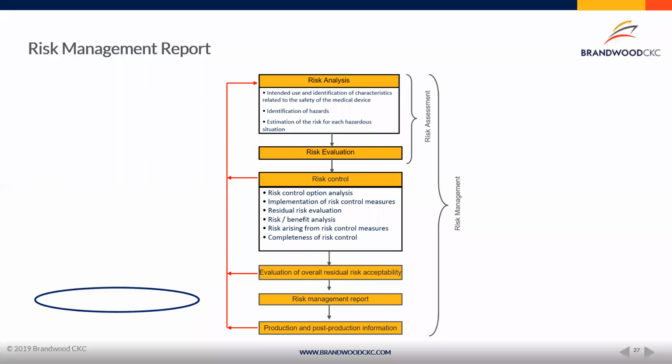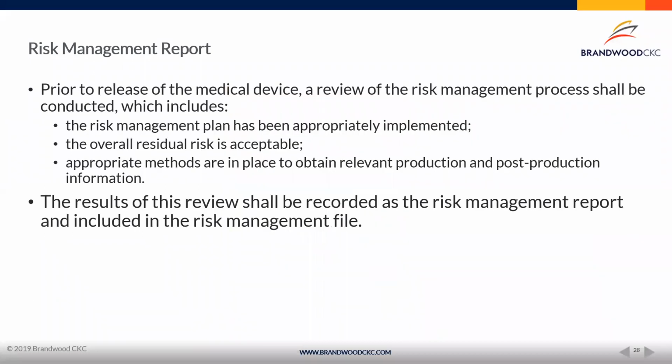Finally, or nearly finally, you create a risk management report. So this risk management report is before the release of the device. You've reviewed all of the risk management processes, and that includes the risk management plan, the residual risk, and any risk controls. So once those have been reviewed and are acceptable to the XFT, which is appropriately able to determine that they're good to go, then you can create this report.